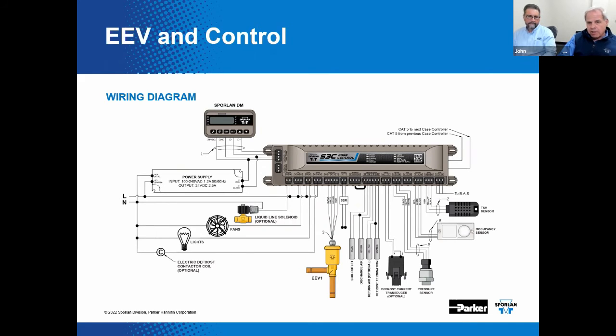Now here's the wiring diagram for that combination. This is the relatively simple wiring diagram for this method of temperature control. Note the presence of a power supply, the display module. Now where'd that liquid line solenoid valve go? There it is. We show how it's wired up with wires entering the junction box there. The EEV, here's the EEV. And then we've got the associated temperature sensors, pressure transducer, and so on. And all the other control functions like fans, lights, defrost, contactor, and so on.